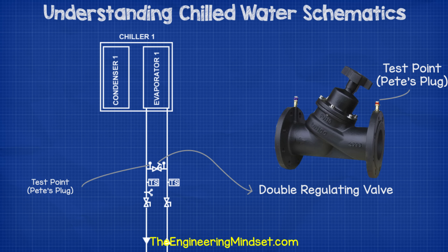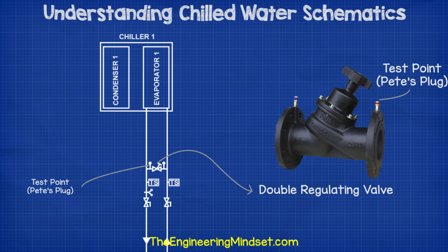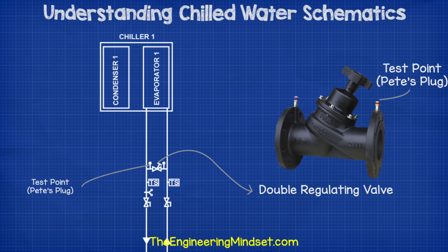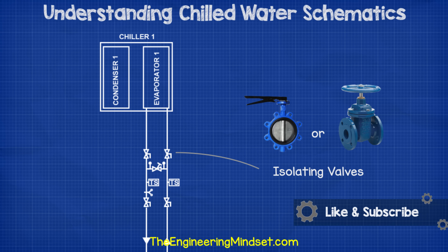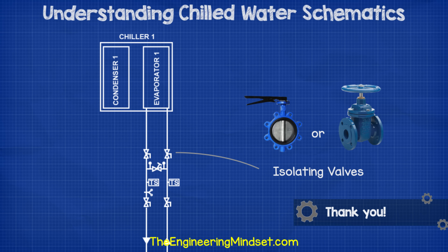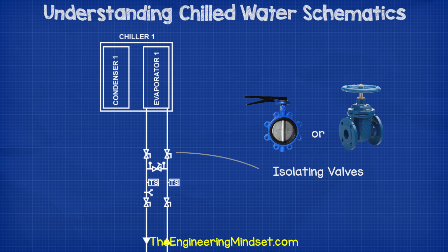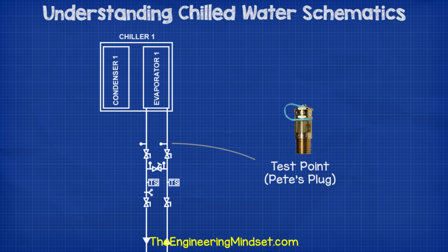Next we have a bypass line, and in this example there's a double regulating valve between the two lines, but it's more common these days to have just an isolating valve here, which is normally closed, or there isn't a bypass line at all. These are used to either flush the system and bypass the chiller to stop dirt going into the heat exchanger during the system clean, or in this case it's used to balance the system as it's an old constant volume system. This can be used to simulate the pressure drop of the chiller if the chiller is isolated for maintenance. Then because we have a bypass line, we'll also have some more isolating valves, which allows the chiller to be cut off from the system but the bypass line can still be used. In newer systems you will find a motorized control valve here, connected to the BMS, which allows remote control. Then we'll have some test points, also known as Pete's plugs, which allow technicians to plug measurement devices in to take temperature and pressure measurements.